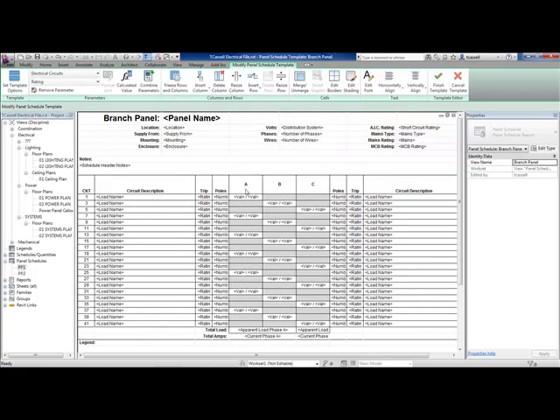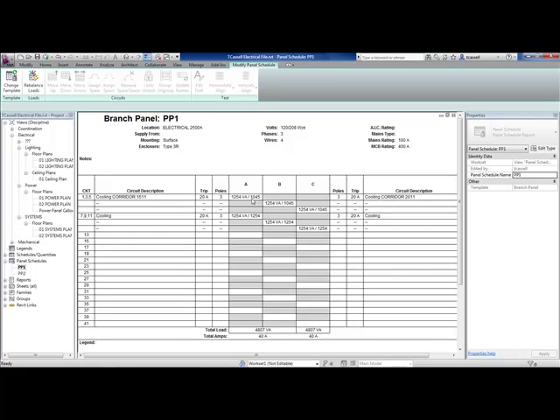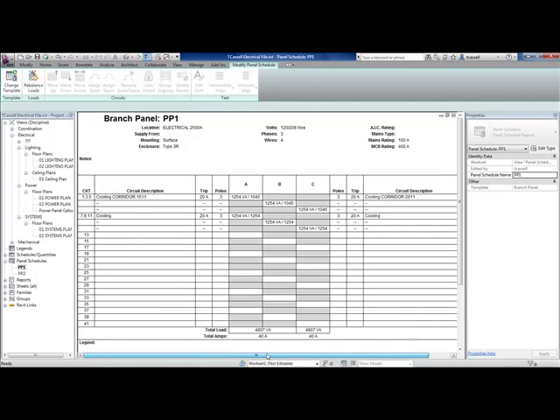When you say okay to that, it makes an adjustment. I can take that adjustment and go to my power panel one and just re-update the template so it now shows my new changes. You can see that I have a load of 1,254 on a three-pole circuit of 1, 3, 5. I have a load of 1,045 on the other side on a three-pole circuit of 2, 4, 6. So now it looks even further the way I want it to look. It's just more flexibility to the panels that you already have a lot of control over.